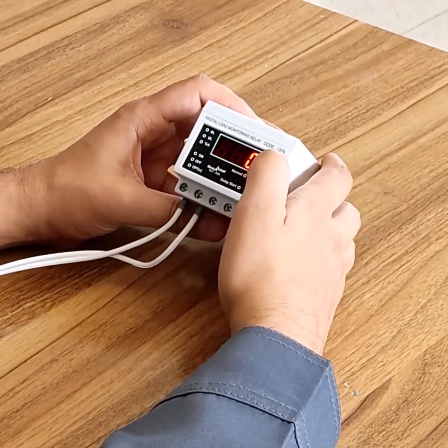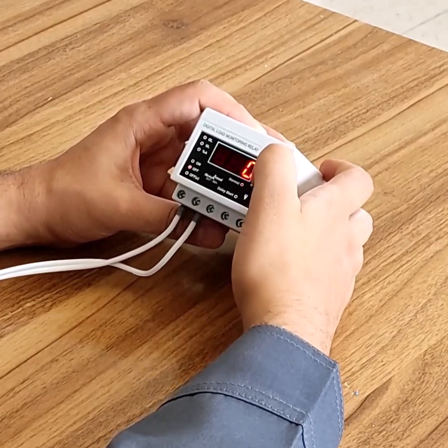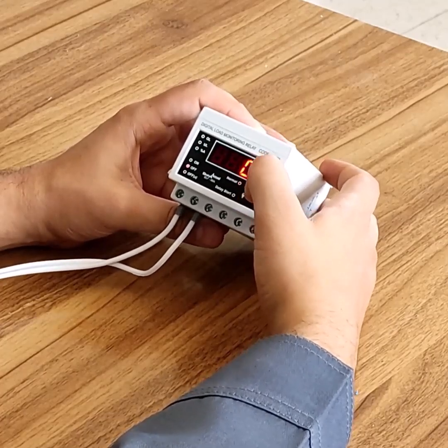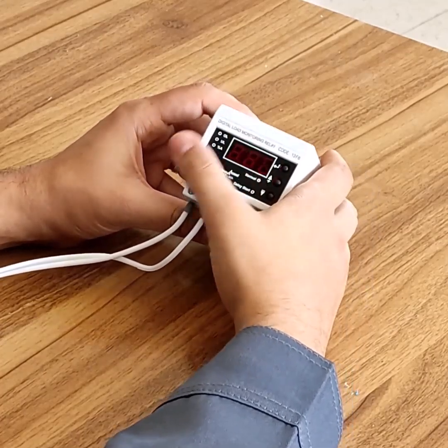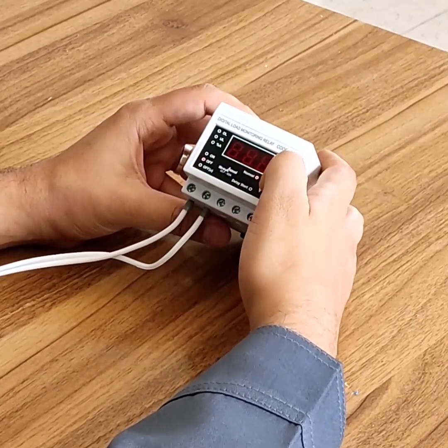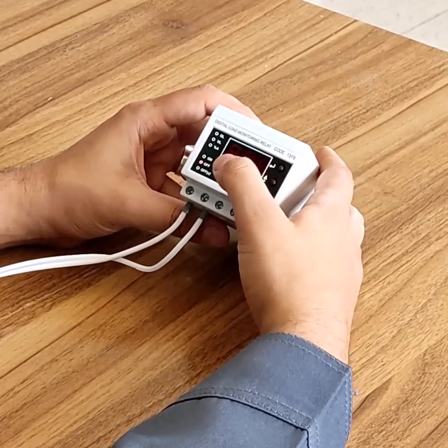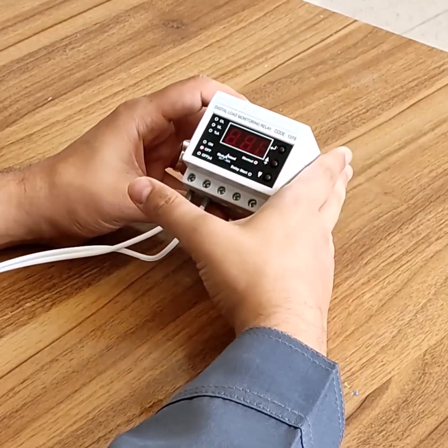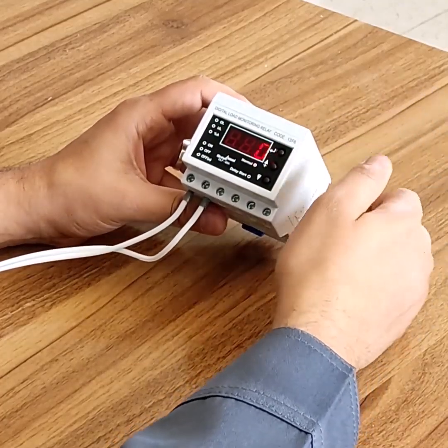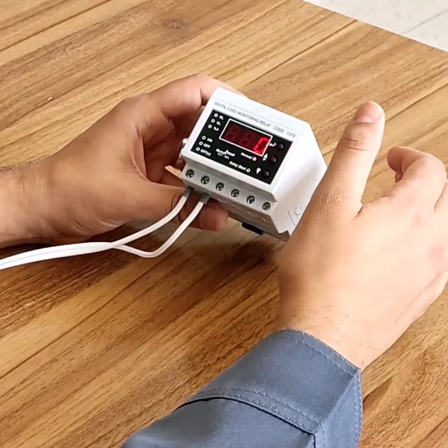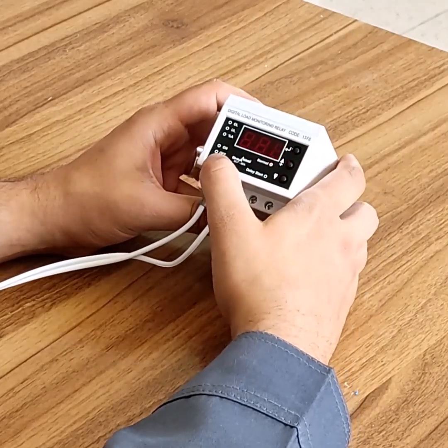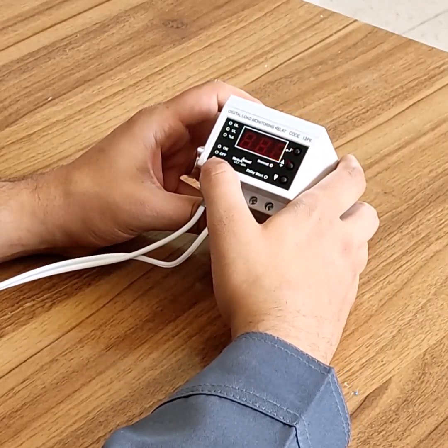The next LED is off, which is a shutdown delay and is a number between 0 and 10. For example, if a current fault occurs by the load, and we have set it to 5 seconds, if not resolved after 5 seconds, it cuts off the command circuit. There are transient errors on the load control, and we only want it to detect and prevent real errors.